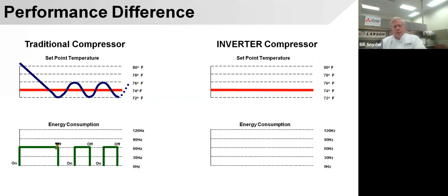Now, with the Mitsubishi inverter, we're not limited to 60 hertz. We can go all the way up to about 125, 130 hertz at times, depending upon the equipment. So in the same scenario, if this is a timeline, we can pull it down colder faster because we're ramping that compressor way up. And I'll show you how we do that as we progress. But we start out very slow like this. We start out very slow and then we ramp it up.